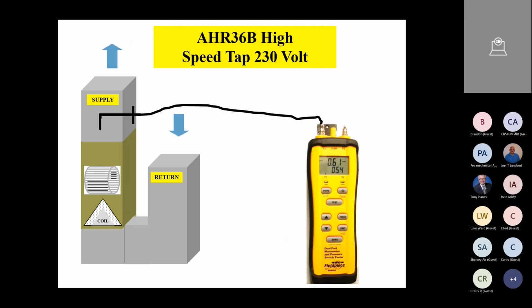Okay. Well, let's go ahead and do another couple examples. In this second example, we've got an AHR 36B. It's on high-speed tap, and we're on the 230-volt portion of that factory airflow chart. So this is just another AHR example on an air handler, high-speed tap, 230-volt portion of the chart. And on this first reading, it looks like we've got a 0.61 on the supply, which is fairly high.